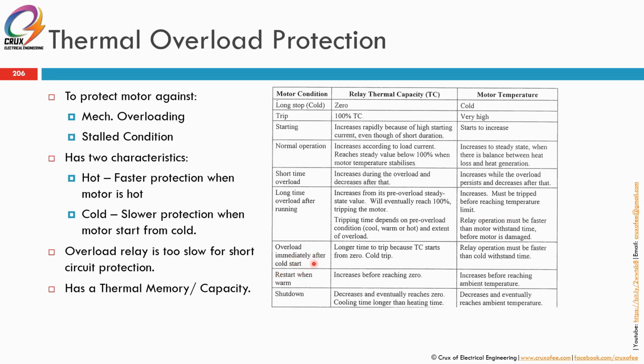While for overload immediately after cold start, it takes a longer time to trip because TC starts from zero, the cold trip. While the relay operation must be faster than the cold withstand time. And for restart when warm, thermal capacity increases from before reaching zero, and motor temperature increases from before reaching ambient temperature. After you shut down, your thermal capacity will decrease and eventually reach zero. Cooling time is typically longer than the heating time, and the temperature decreases and eventually reaches ambient temperature. So to summarize, basically the overload protection which is based on relay thermal capacity is much more sensitive as compared to the winding temperature alone.